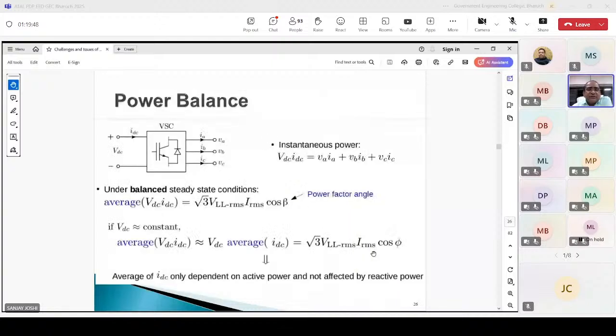Power balance, this is also very important. VSC is here, DC side, AC side. The instantaneous power is VDC, IDC. This equation balances DC power. On the right hand side of the equation, it is AC power. So under balanced steady state condition - I repeat, steady state condition - the average of product of VDC and IDC is root 3 VLL RMS, IRMS, and cosine beta, that is the power factor angle. On both sides of this equation, there is active power.